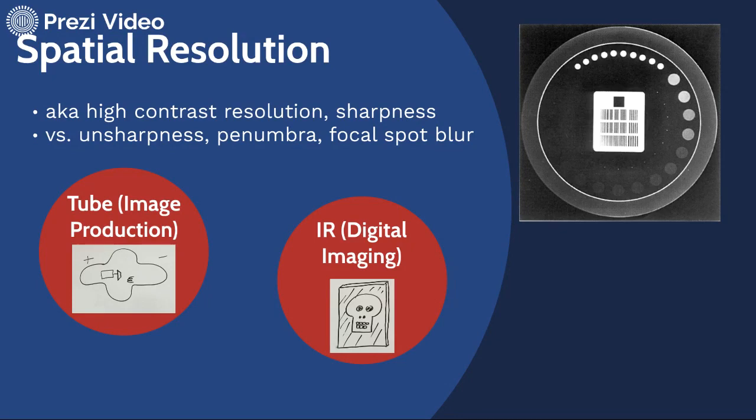Spatial resolution has a bunch of different ways that we might talk about it. We might talk about it as high contrast resolution. We might also refer to it as sharpness, and sharpness isn't actually a measurable term, but we sometimes compare it versus unsharpness or penumbra, and these are actually measurable geometrical things. They oftentimes are under the umbrella of what we call focal spot blur. So let's talk about that from the standpoint of the x-ray tube.